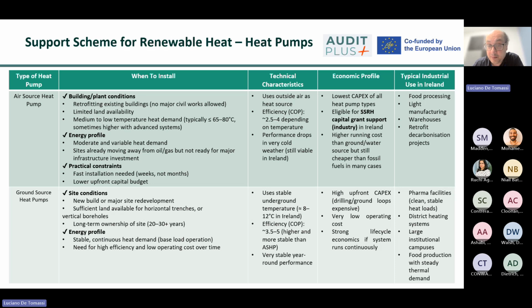with backup heating systems. Ground source heat pumps extract heat from the ground through boreholes or horizontal loops and provide more stable and typically higher efficiency performance due to relatively constant subsurface temperatures. They are best suited to buildings or industrial sites with high and relatively continuous baseload heat demand, such as hospitals, large commercial facilities, or industrial processes operating year-round. This stability makes them particularly attractive for applications where long-term efficiency is prioritized over lower upfront costs.